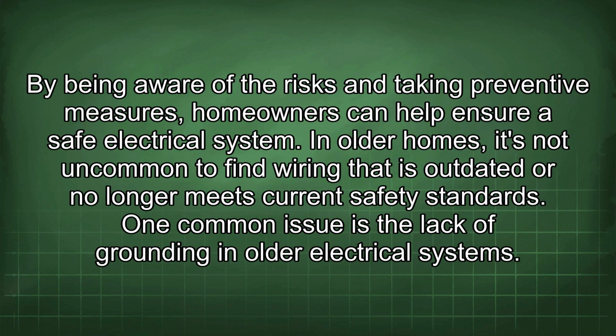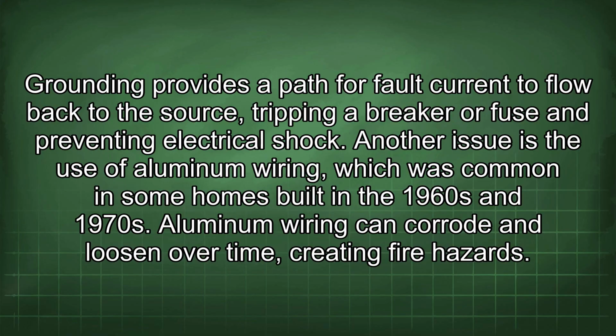By being aware of the risks and taking preventive measures, homeowners can help ensure a safe electrical system. In older homes, it's not uncommon to find wiring that is outdated or no longer meets current safety standards. One common issue is the lack of grounding in older electrical systems. Grounding provides a path for fault current to flow back to the source, tripping a breaker or fuse and preventing electrical shock. Another issue is the use of aluminum wiring, which was common in some homes built in the 1960s and 1970s. Aluminum wiring can corrode and loosen over time, creating fire hazards.